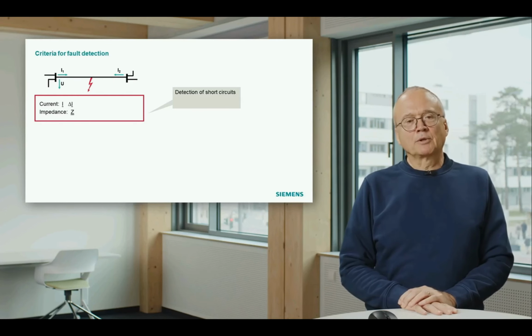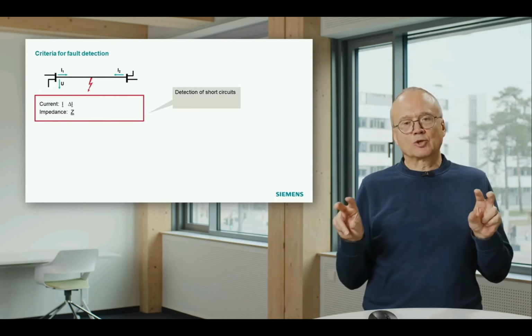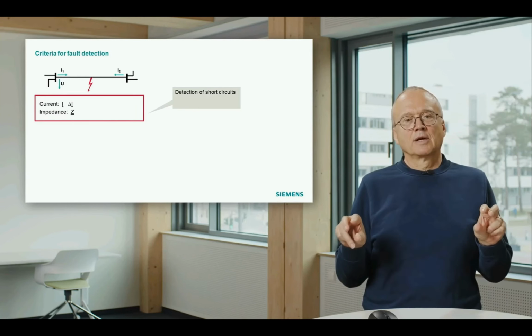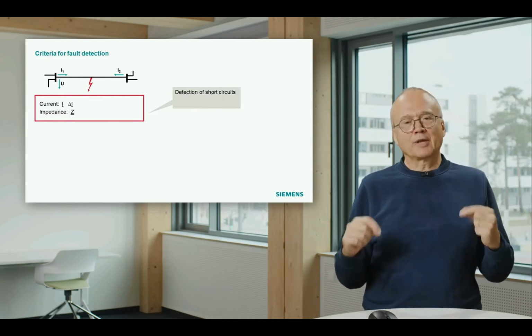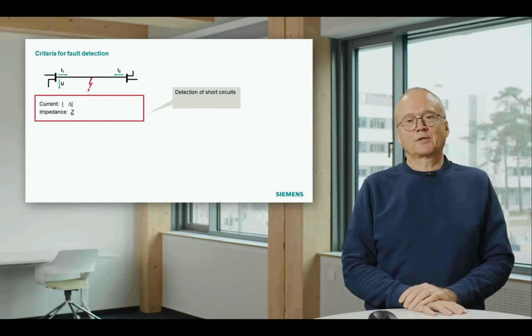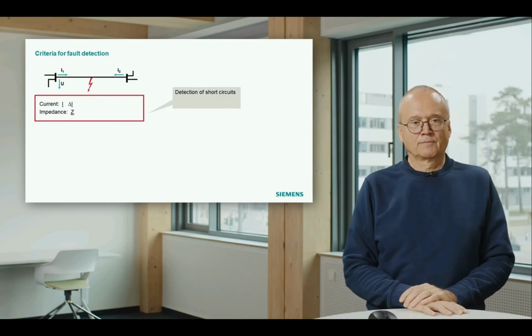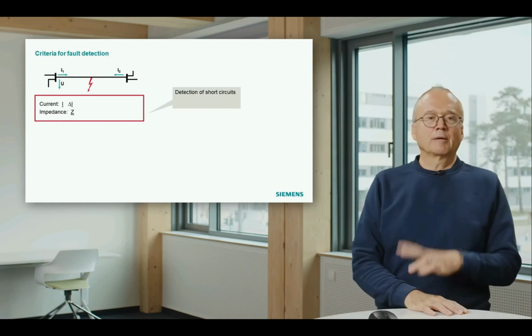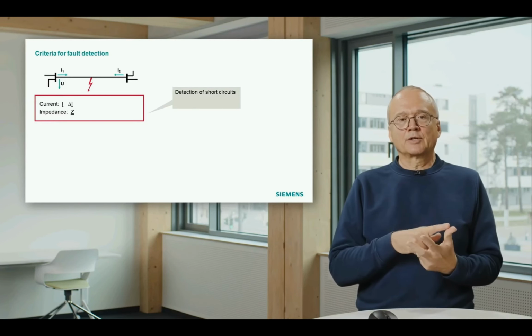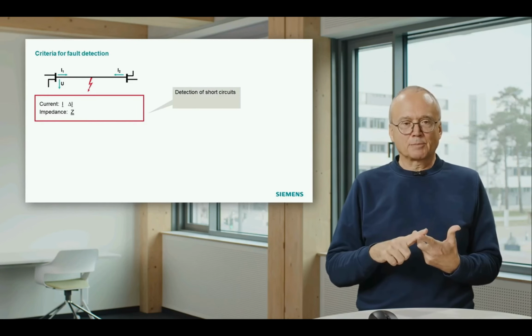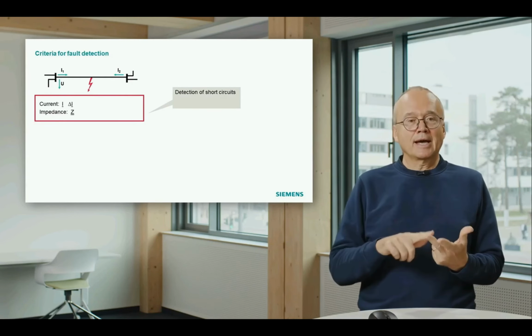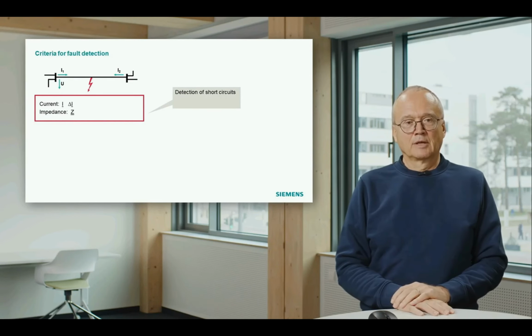And the third principle is based on a current difference. That means we measure the current at 2 different locations and compare them, and from that we try to find out: is there a fault on the line or not? That principle is called the current differential protection. That means we have three different principles to detect short circuits: the overcurrent principle, the distance principle based on the impedance, and the current differential.